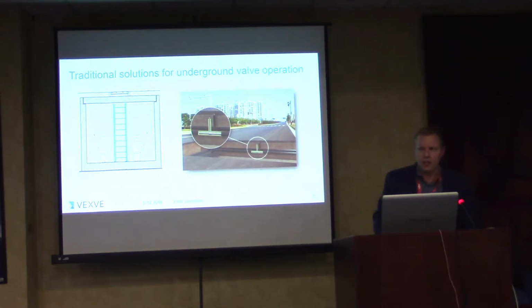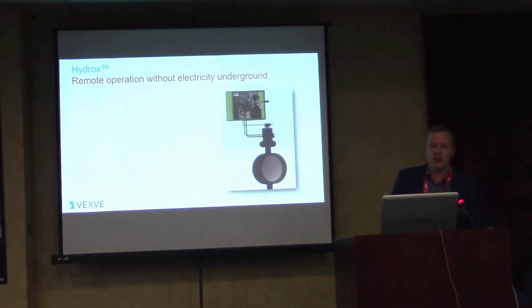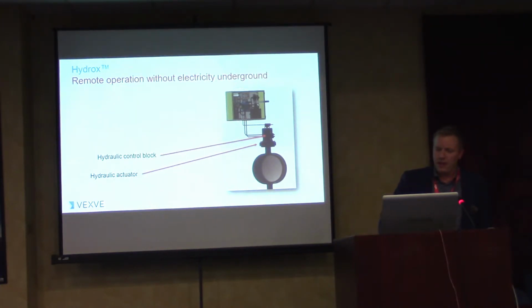What we have been promoting for several years now is hydraulic operation of valves. We produce these hydraulic actuators ourselves, which we call Hydrox. The principle of the hydraulic actuator on a district heating valve is: on the valve we have a hydraulic actuator and hydraulic control block. In case there is anything wrong with these hydraulic hoses, it will immediately stop the flow of hydraulic oil from inside the actuator, thus keeping, for example, the butterfly valve in the same position.